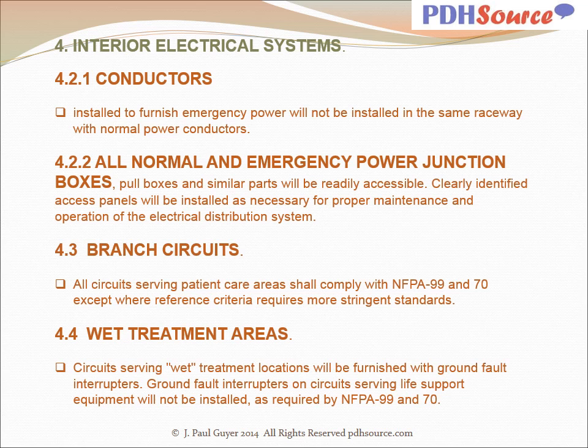Conductors installed to furnish emergency power will not be installed in the same raceway with normal power conductors. All normal and emergency power junction boxes, pull boxes, and similar parts will be readily accessible. Clearly identified access panels will be installed as necessary for proper maintenance and operation of the electrical distribution system. All circuits serving patient care areas shall comply with NFPA 99 and 70, except where reference criteria requires more stringent standards. Circuits serving wet treatment locations will be furnished with ground fault interrupters. Ground fault interrupters on circuits serving life support equipment will not be installed as required by NFPA 99 and 70.